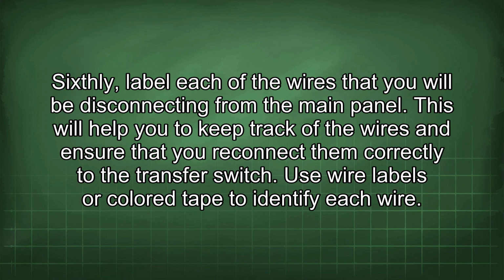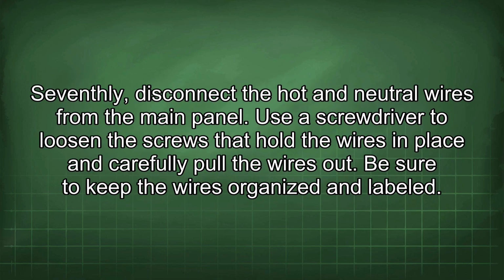This will help you to keep track of the wires and ensure that you reconnect them correctly to the transfer switch. Use wire labels or colored tape to identify each wire. Seventhly, disconnect the hot and neutral wires from the main panel. Use a screwdriver to loosen the screws that hold the wires in place and carefully pull the wires out. Be sure to keep the wires organized and labeled.